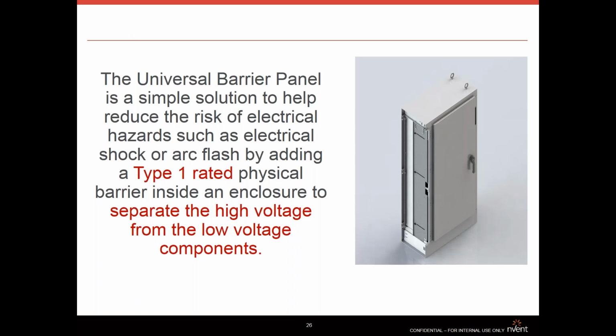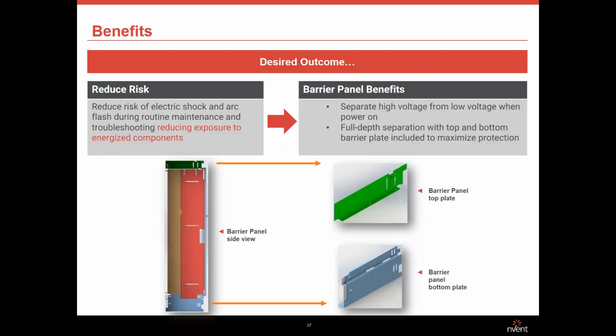So the HOFFMAN Universal Barrier Panel is a simple solution to help reduce the risk of electrical hazards such as electrical shock and arc flash by adding a Type 1 rated physical barrier inside the enclosure so that we can separate the high voltage and the low voltage components, as well as multi-voltage enclosures. This will help us reduce the risk of electric shock and arc flash during routine maintenance by separating the high voltage and low voltage when the power is on. It gives us full depth separation, and that's one of the things that we have with the Type 1 enclosure barrier panel. We have that full depth separation, both top and bottom as well as front to back.